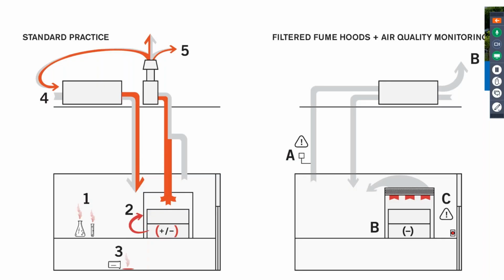Now, in a building with lab space, which even a lot of high schools have, it can be a big driver in terms of the energy consumption. And so we needed to address that. Standard practice would be 6 air changes per hour all the time, and ducted fume hoods exhausting to the atmosphere with mediocre heat recovery systems typically.